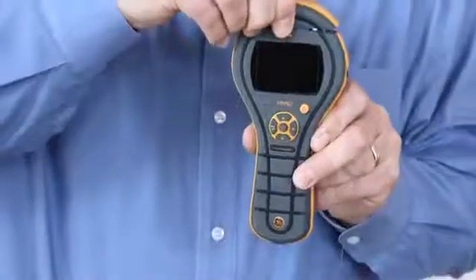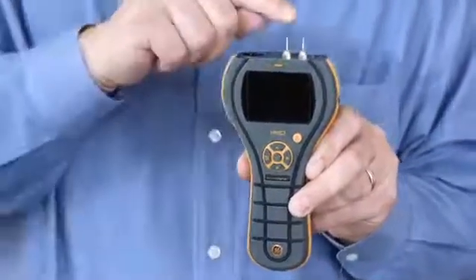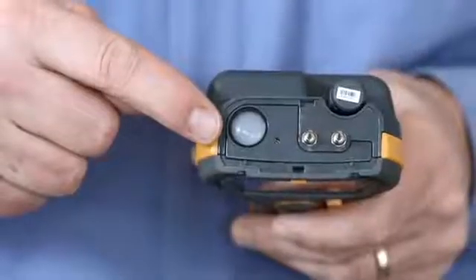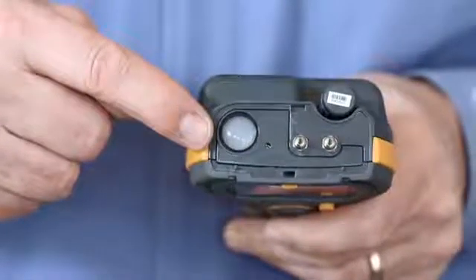I'm going to remove the cap, and the first thing you'll notice is that we now have pins on the top of the instrument. This makes it extremely convenient for taking moisture measurements without plugging in accessories. Also in the top of the meter here, you'll see the non-contact surface infrared thermometer, and there's a laser pointer for this as well.